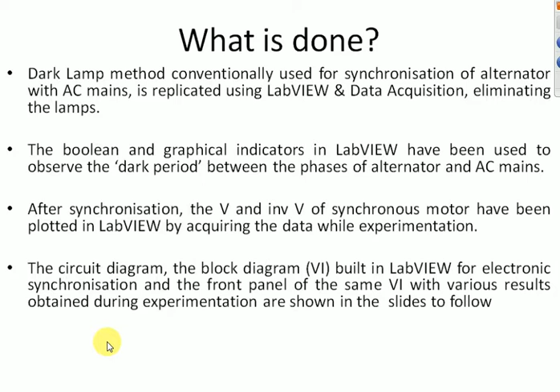Instead, we went with the approach of using virtual instruments and Boolean knobs, so that if and when certain conditions are satisfied, you can close the switch isolating the generator from the bus or power supply. This is the counterpart of dark lamp synchronization, which we have been doing for 50 years, but here done electronically through Boolean controls and graphical indicators in LabVIEW, as you'll see in the next slide.